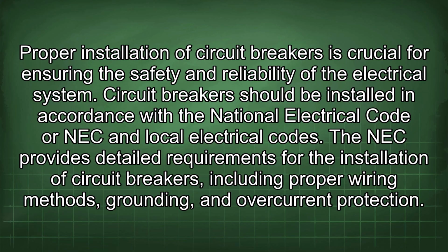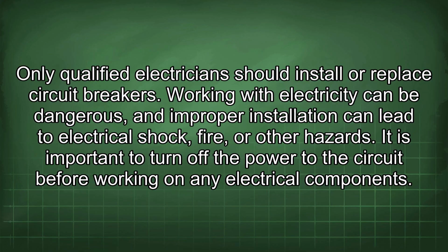Circuit breakers should be installed in accordance with the National Electrical Code, or NEC, and local electrical codes. The NEC provides detailed requirements for the installation of circuit breakers, including proper wiring methods, grounding, and overcurrent protection. Only qualified electricians should install or replace circuit breakers. Working with electricity can be dangerous, and improper installation can lead to electrical shock, fire, or other hazards.